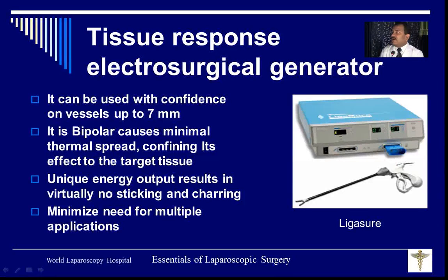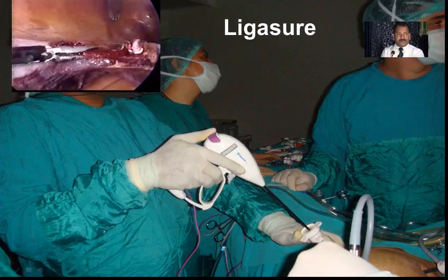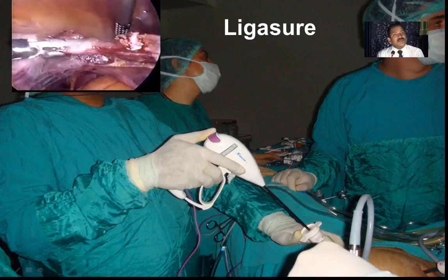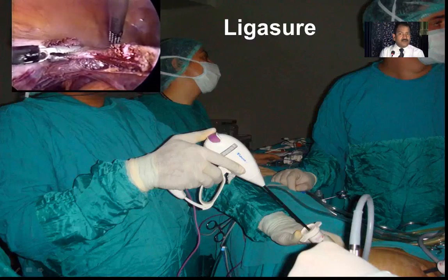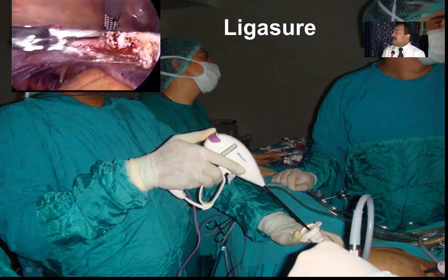And they removed all the buttons from their machine. There is no more setting left for the doctors. And this is called a tissue response electrosurgical generator. Tissue response means it can talk with the tissue. It can take the response from the tissue. And as soon as you touch the tissue, it goes ting tong, stop. That means it is good. So you have to press and wait.